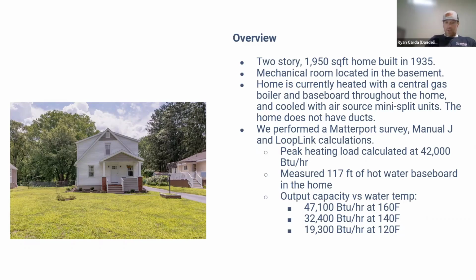We also measured all of the baseboard radiators throughout the house, understanding the type of radiator, so you can quantify how much heat you can get out of those radiators as a function of delivery temperature. On screen you can see it takes about 160-degree water to meet the heating needs of the building on the coldest day of the year, and you can see how that radiator output capability tails off pretty quickly with lower delivery temperatures.